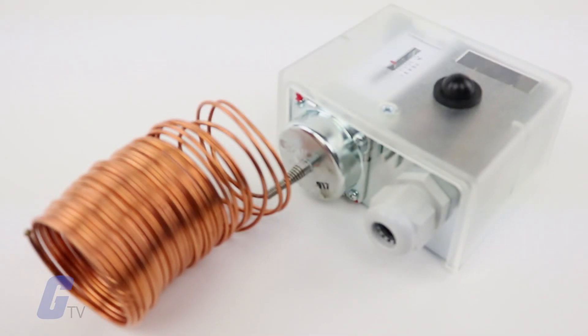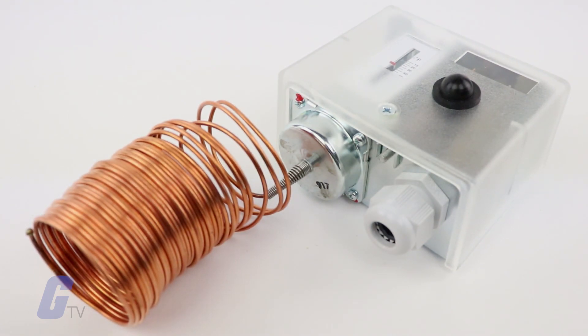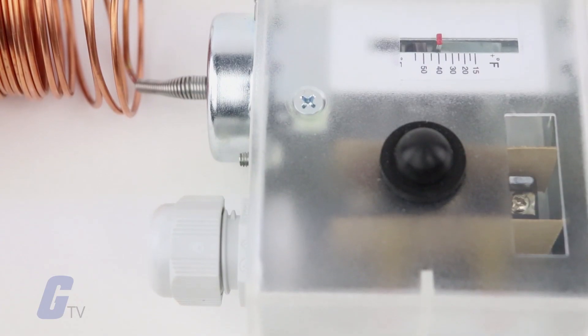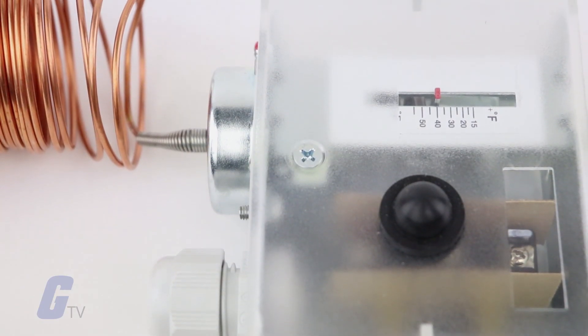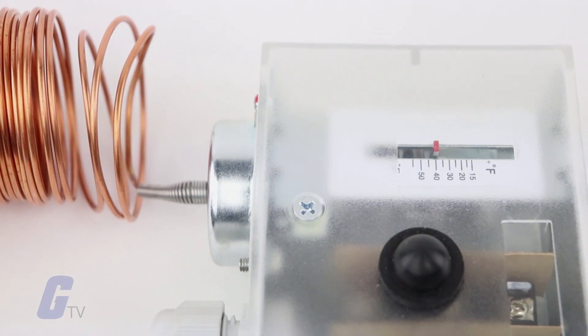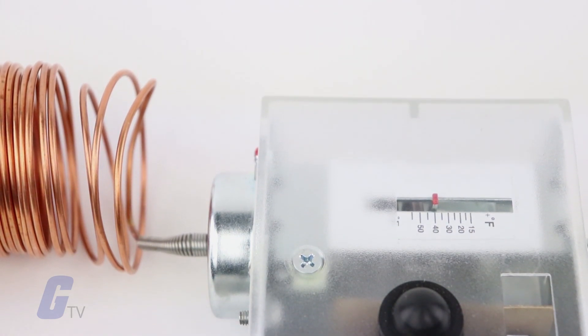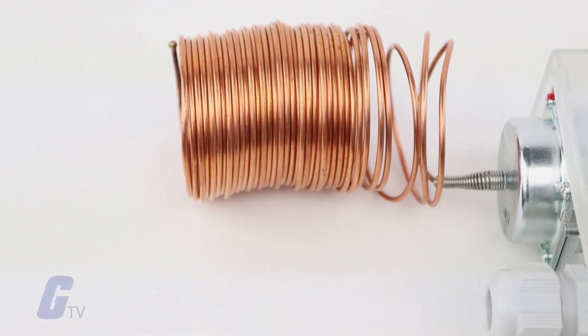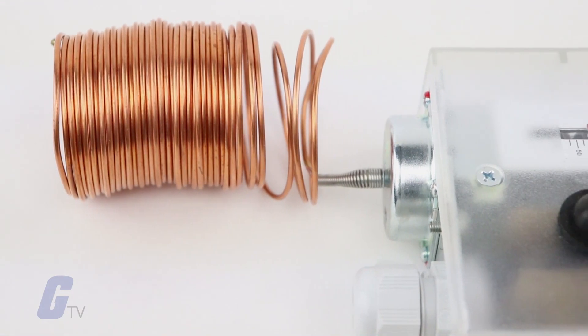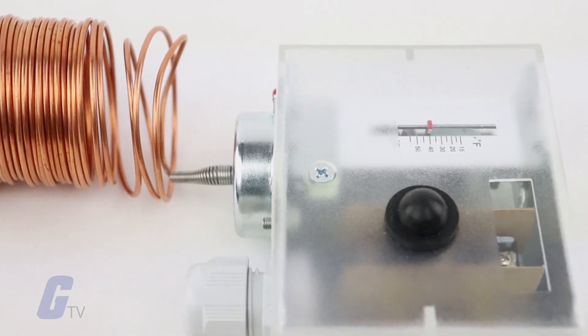They should be mounted between the heating and cooling coils on the supply side of the fan unit. They respond to the lowest temperature sensed along any one-foot section of the sensing element.